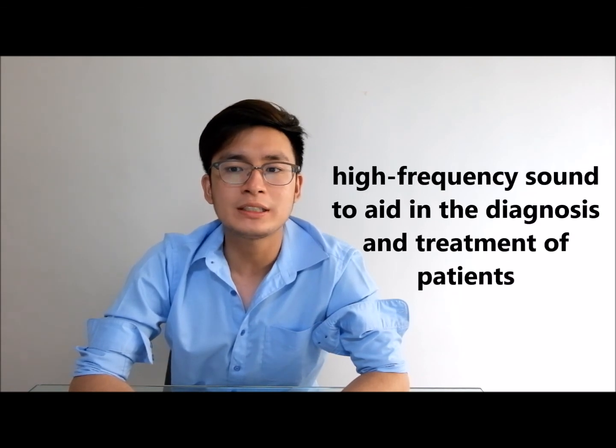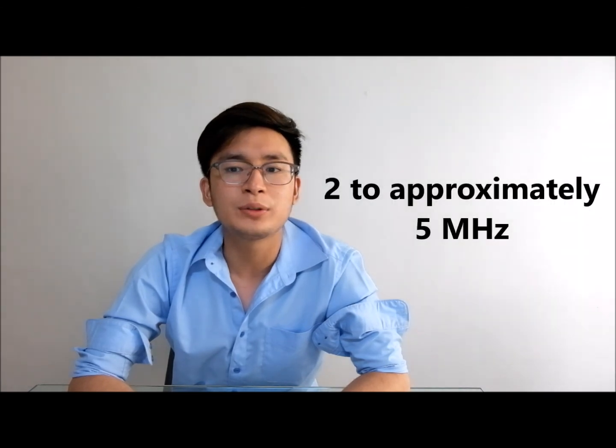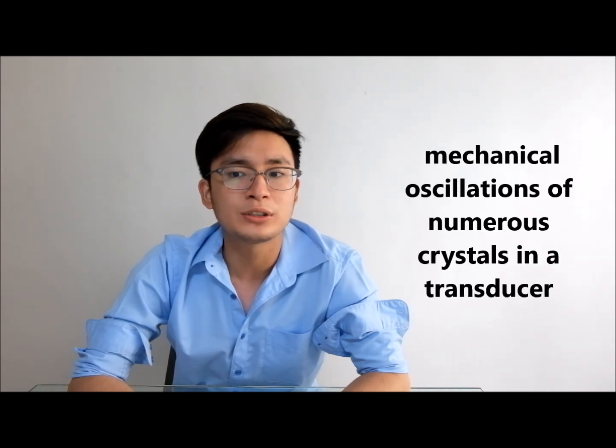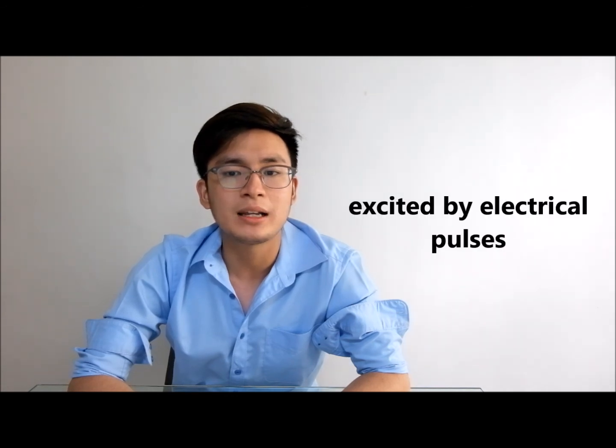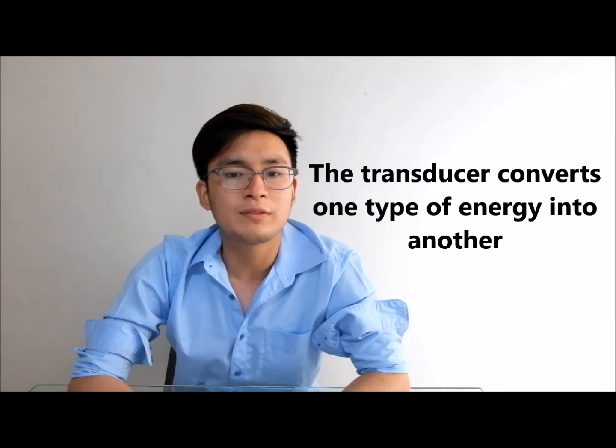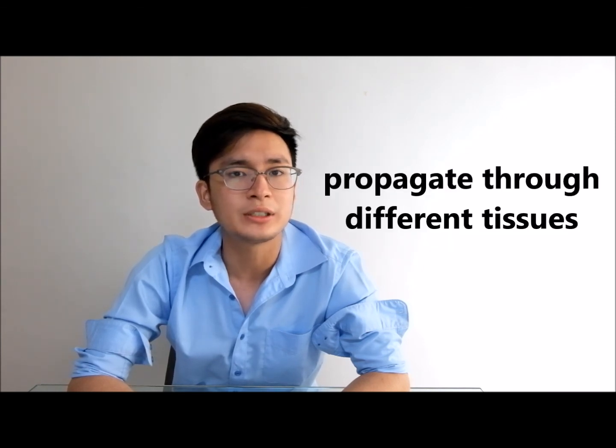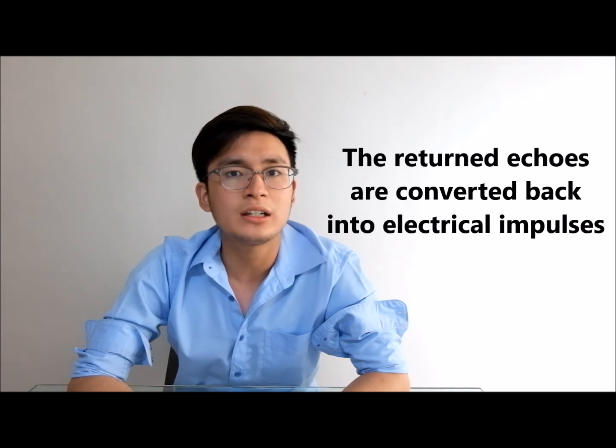Pulse of ultrasound. Medical ultrasound is based on the use of high-frequency sound to aid in the diagnosis and treatment of patients. The ultrasound frequencies range from 2 to approximately 5 MHz, although even higher frequencies may be used in some situations. The ultrasound beam originates from mechanical oscillations of numerous crystals in a transducer, which is excited by electrical pulses. The transducer converts one type of energy into another. Ultrasound waves are sent from the transducer, propagated through different tissues, and then return to the transducer as reflected echoes. The returned echoes are converted back into electrical impulses by the transducer's crystals and are further processed to form the ultrasound image and presented on the screen.